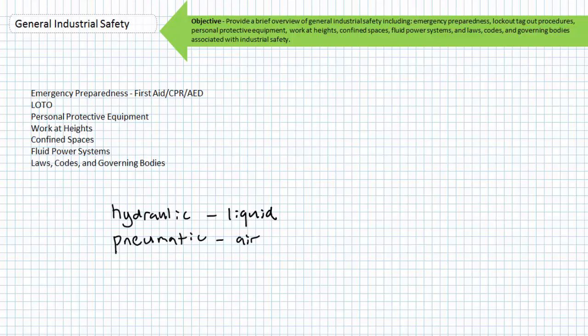An injection injury is when high pressure forces oil into your body. Such an injury may require amputation or involve surgery. Immediately shut down a hydraulic system if you discover a pinhole leak. Spilled oil presents an obvious fall hazard as well as an environmental concern. Material safety data sheets should accompany all systems and make abundantly clear any special precautions.